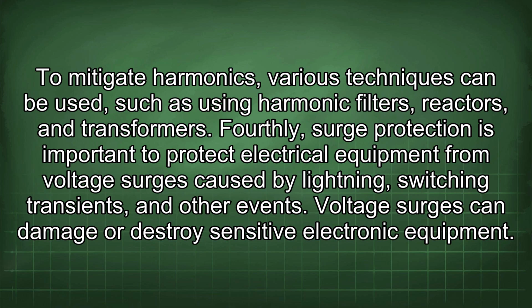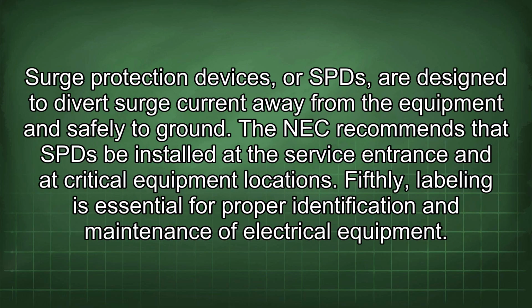Fourthly, surge protection is important to protect electrical equipment from voltage surges caused by lightning, switching transients, and other events. Voltage surges can damage or destroy sensitive electronic equipment. Surge protection devices, or SPDs, are designed to divert surge current away from the equipment and safely to ground. The NEC recommends that SPDs be installed at the service entrance and at critical equipment locations.